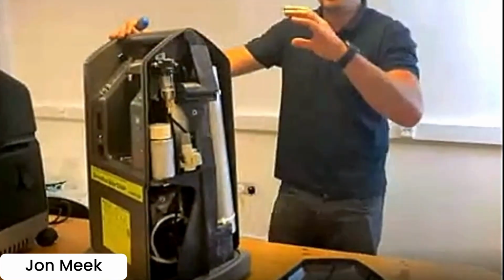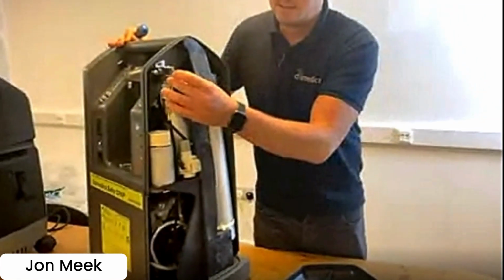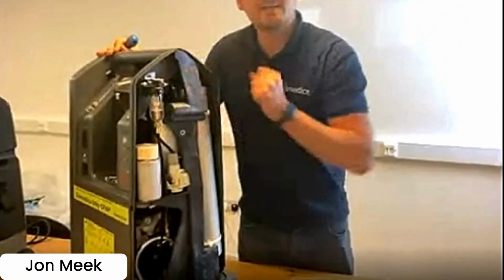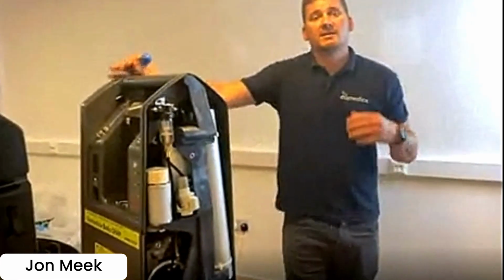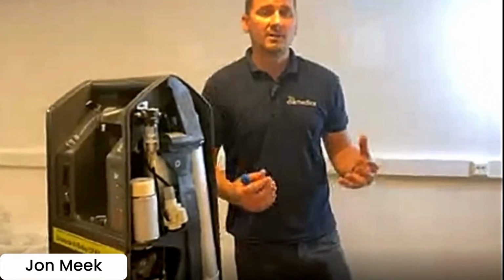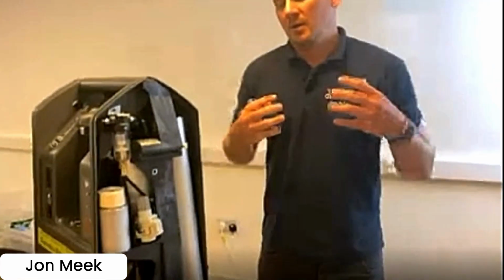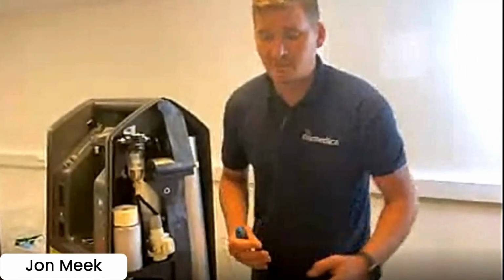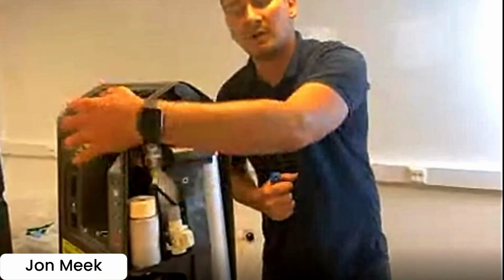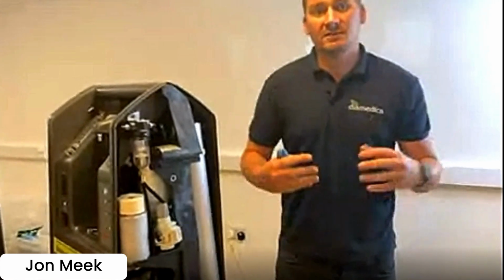So we're taking off the compressor, but more importantly, what we realized going through time, and you'll see it on the new one, is we had to fit a water trap, a self-draining water trap, because in the humidity and environments these are going to be working in, air generated from the compressor produces a lot of moisture. So all the moisture going through, the last thing we want to do is put it through to the flow meter. Humidification is obviously key, which is good.